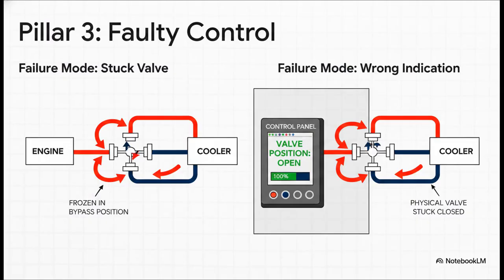Here, your pumps might be strong, your coolers might be clean, but the brain of the system is making bad decisions. A three-way thermostatic valve that's stuck in bypass is just sending hot water right back to the engine instead of through the cooler. An actuator can send a signal to the control room saying it's open when it's physically jammed shut. These control failures are confusing because water is still moving. It's just going down the wrong path.